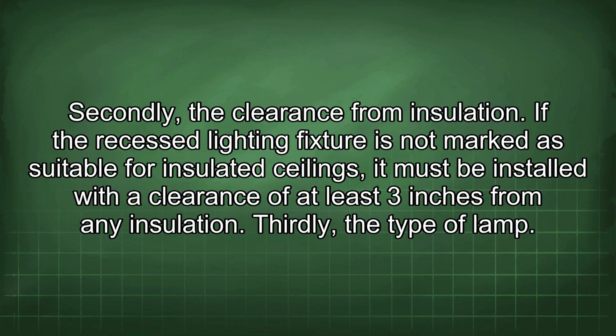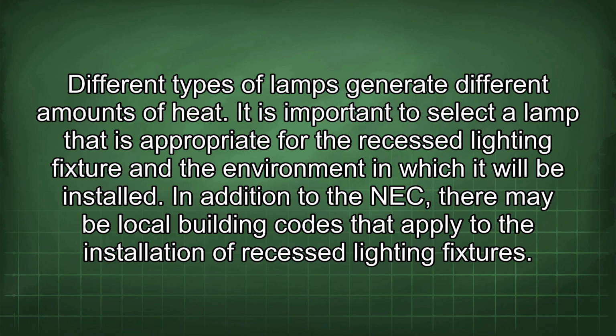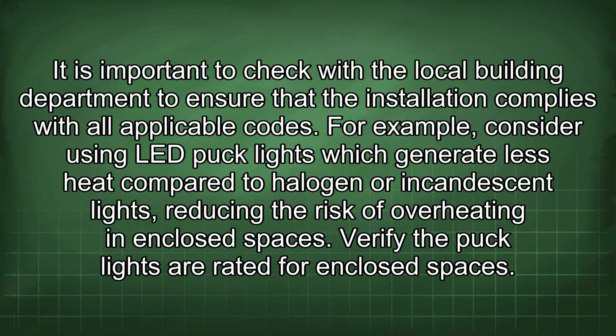Thirdly, the type of lamp. Different types of lamps generate different amounts of heat. It is important to select a lamp that is appropriate for the recessed lighting fixture and the environment in which it will be installed. In addition to the NEC, there may be local building codes that apply to the installation of recessed lighting fixtures.